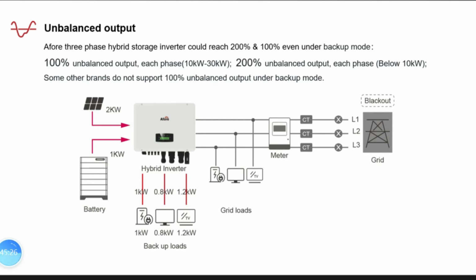So it's a three-phase hybrid inverter. When the grid is down, they can deliver emergency power to three-phase loads. But in our home, the load is not always three-phase. We also have some single phase loads to connect. So in that case, it will cause energy imbalance for each phase. So within this design, even under the EPS mode, the system works, and the inverter can handle this kind of difference in energy for each phase.